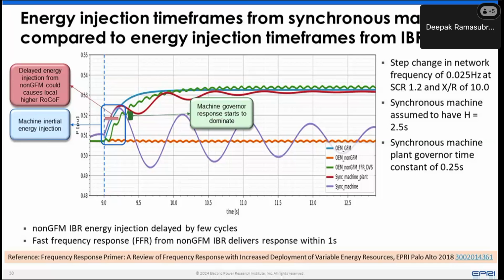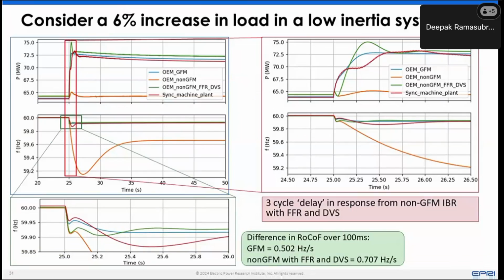Going to the next slide, you can get a little more insight into how these actually impact the system. If you consider a system and see a 6% increase in load in this low inertia system, then at the high level you see very similar performance in frequency, irrespective of whether you have grid forming or fast frequency response. Now, if you dig into the details, looking at the first 1.5 seconds, you do start seeing a little bit of a difference in the response between these various resources, as shown on the right-hand side of the figure. If you look at the frequency, you have to zoom in quite a bit to see the difference. And if you zoom out and look at the nadir of the frequency response, they align quite well.